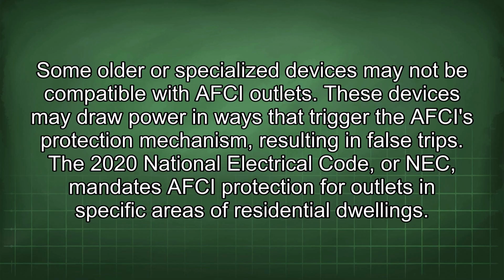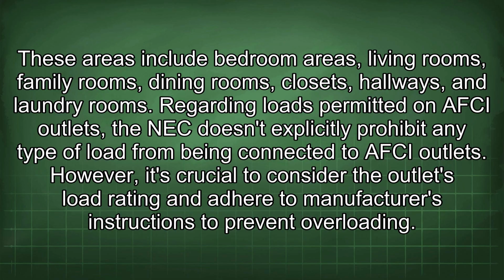The 2020 National Electrical Code, or NEC, mandates AFCI protection for outlets in specific areas of residential dwellings. These areas include bedroom areas, living rooms, family rooms, dining rooms, closets, hallways, and laundry rooms. Regarding loads permitted on AFCI outlets, the NEC doesn't explicitly prohibit any type of load from being connected to AFCI outlets. However, it's crucial to consider the outlet's load rating and adhere to manufacturers' instructions to prevent overloading.